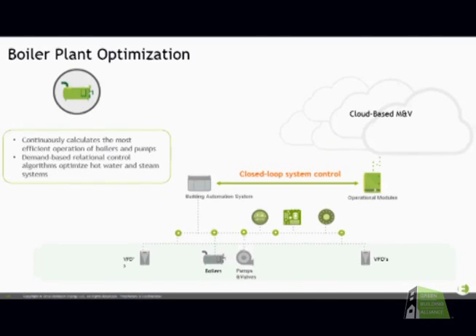The question you're asking is asked by a lot of people trying to do optimization who want to understand why there's another box, why do this? If you think of air compressors, like a Gardner-Denver system, it's a separate system from the one just maintaining the pressure. It's the one staging, looking at demand, looking at the cost of electricity at the time, things like that. So it's like the energy-based BAS, with things like kW per ton, BTUs per GPM, coming out, as opposed to just simple, typical control-based sequence numbers.